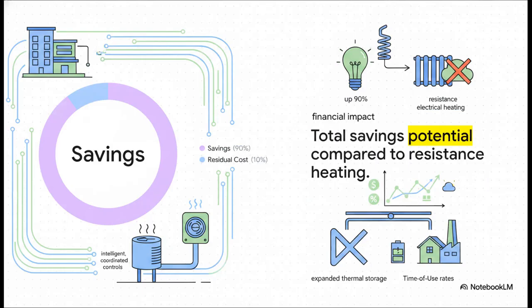When you combine that expanded thermal storage with intelligent, coordinated controls, the financial impact is staggering. In markets that utilize time-of-use rates and demand charges, this exact system can achieve up to 90% savings compared to traditional resistance electrical heating. That's a massive cost saving for the customer and a vital, reliable load-shifting tool for the utility company.